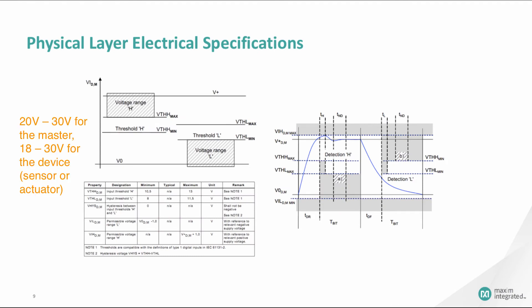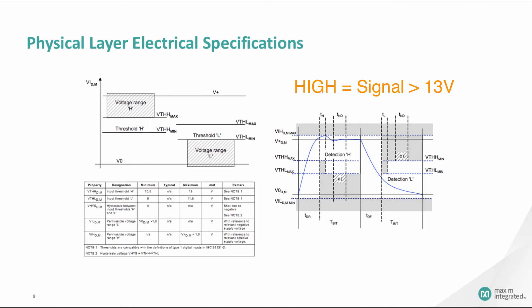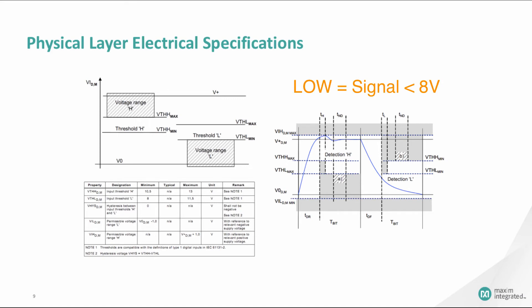The supply range is 20 to 30 volts for the master and 18 to 30 volts for the device. A rising IO-Link signal must go above 13 volts to be registered as a high. A falling IO-Link signal must go below 8 volts to be registered as a low. The high and low detection times — TH and TL in the timing diagram — are at least one-sixteenth of a bit. TND, the noise suppression duration, must be less than one-sixteenth of a bit.